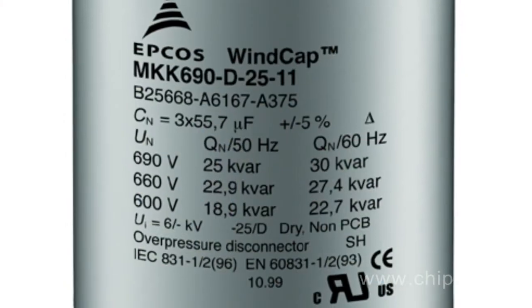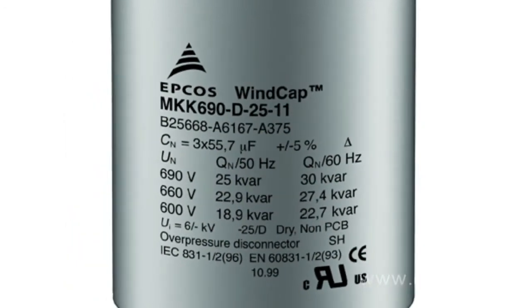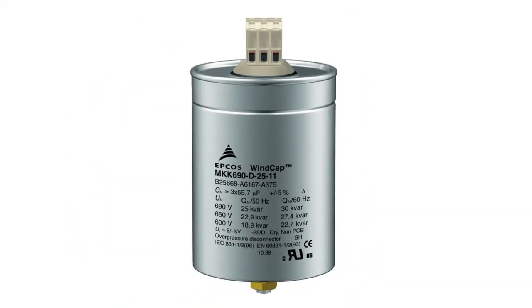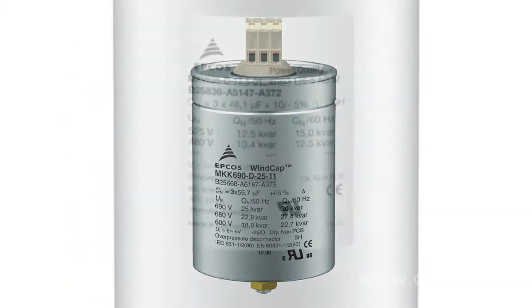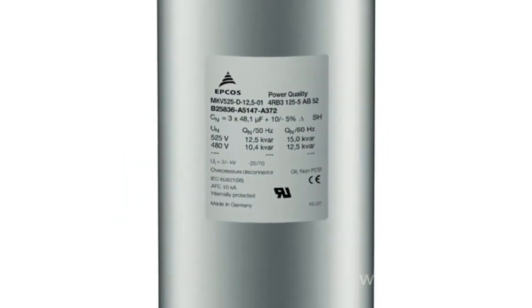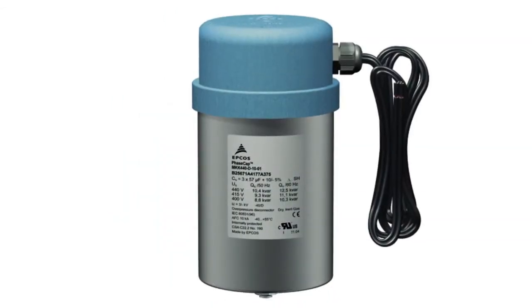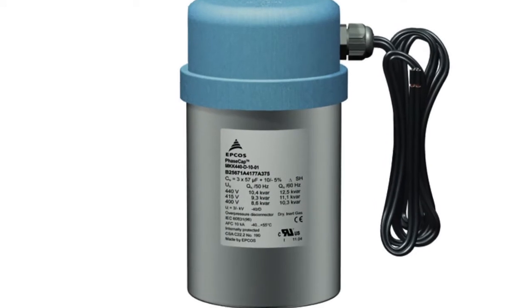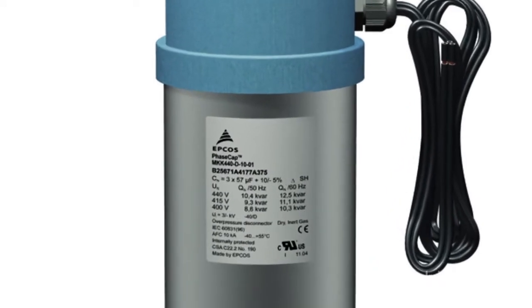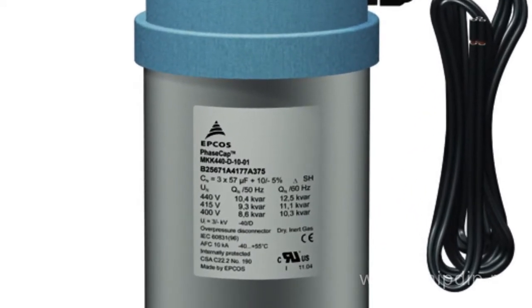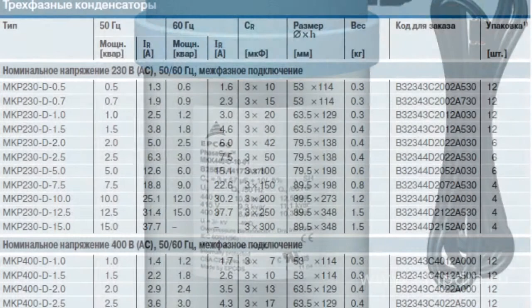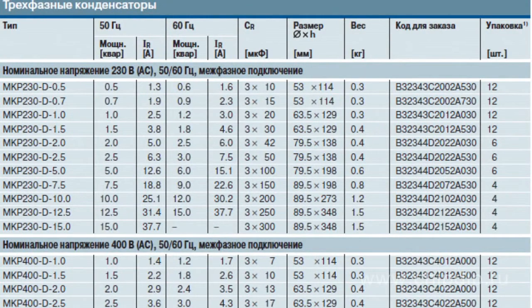To select a proper capacitor for a power factor correction system, we need to consider a whole number of factors that affect its parameters and service life. This includes voltage, harmonic distortion, temperature, RMS current value, and inrush current at connection.